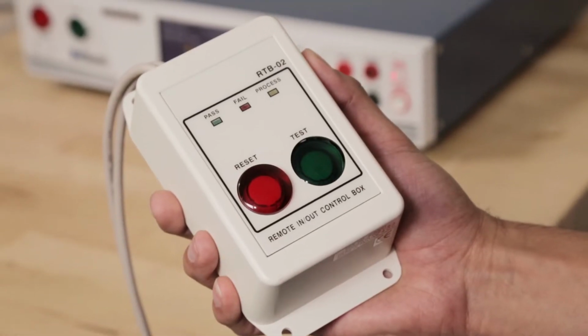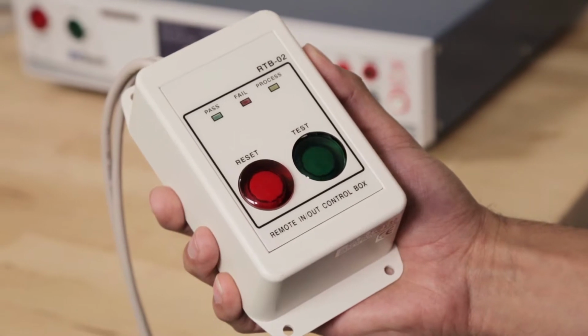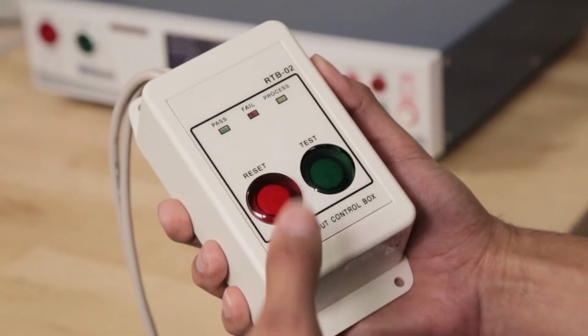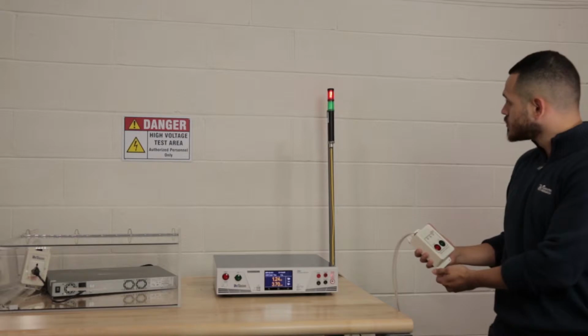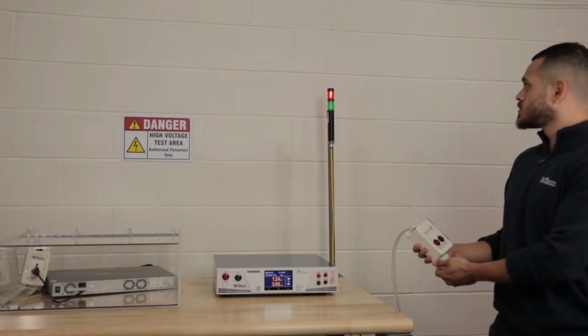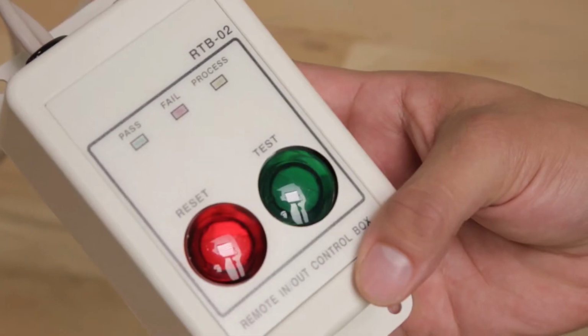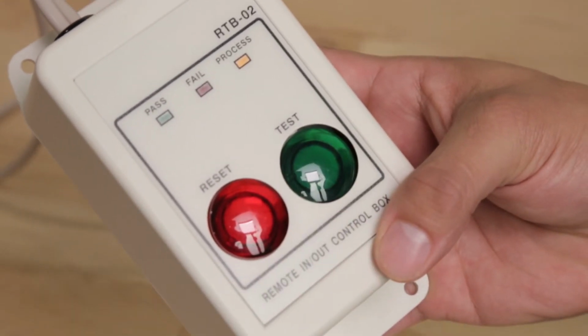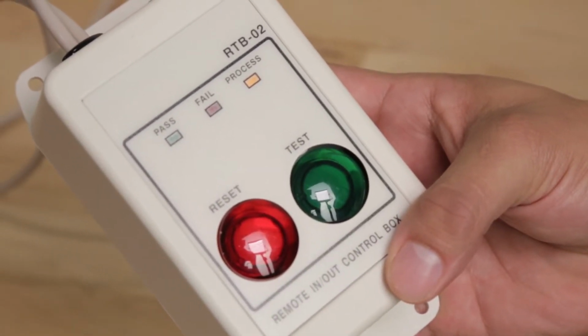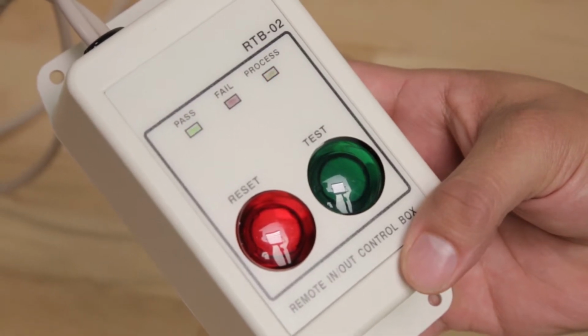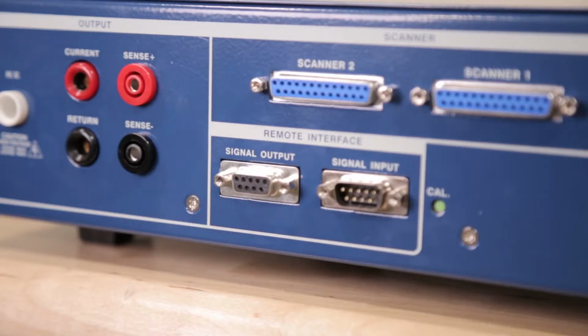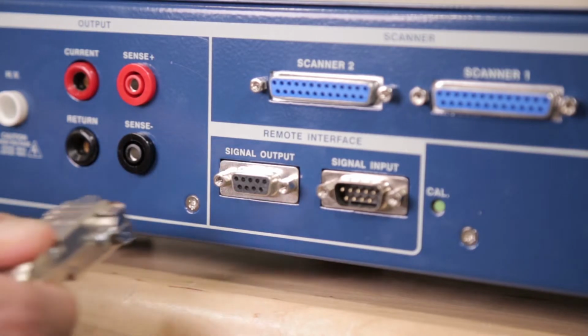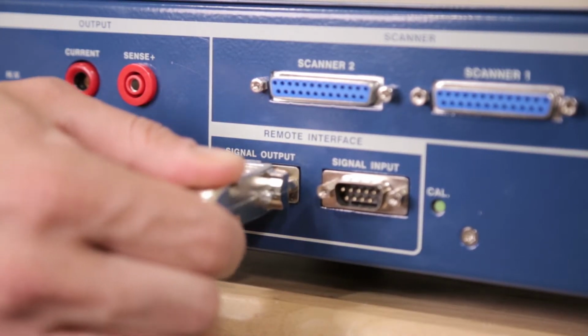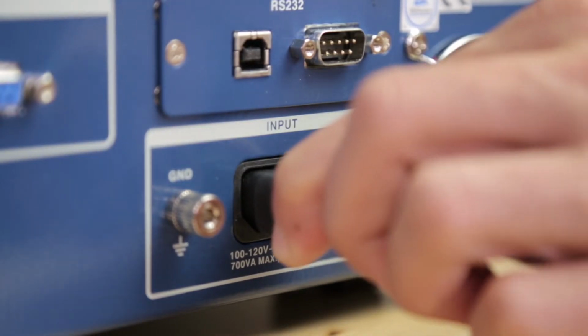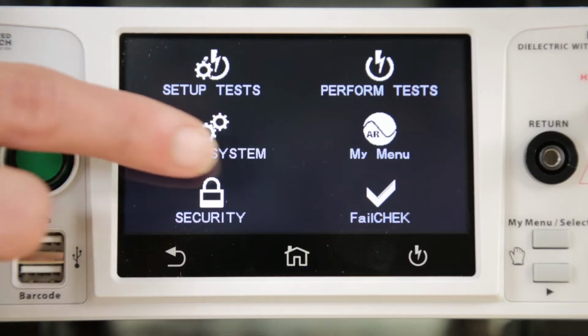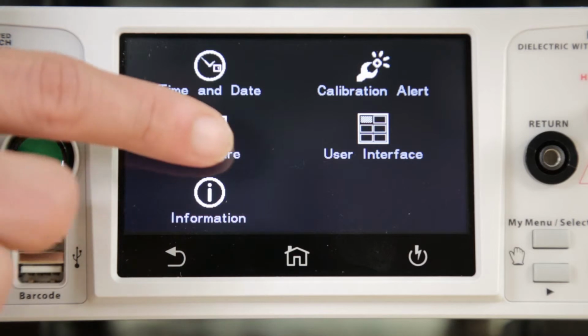Using a remote test box, such as our RTB-02, allows a test operator to stand at a safe distance from the test area, while still having the ability to initiate or abort a test. The RTB-02 has 3 LEDs, which display each stage of the electrical safety test. To connect the RTB-02, attach the 2 cables of the RTB-02 to the signal I/Os of the instrument. You'll also need to power on the instrument. Select Setup System, Hardware, and the PLC setting On.